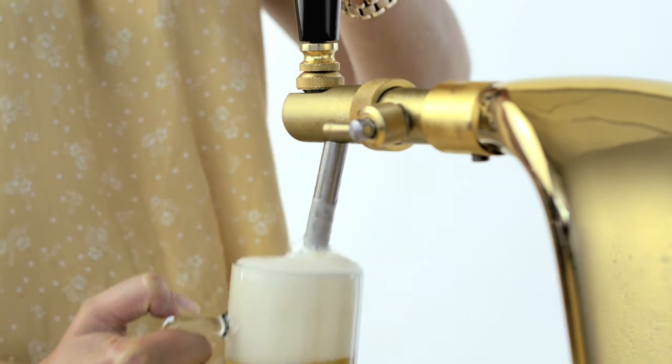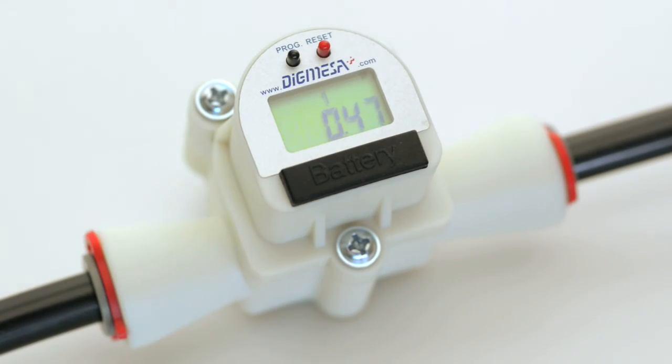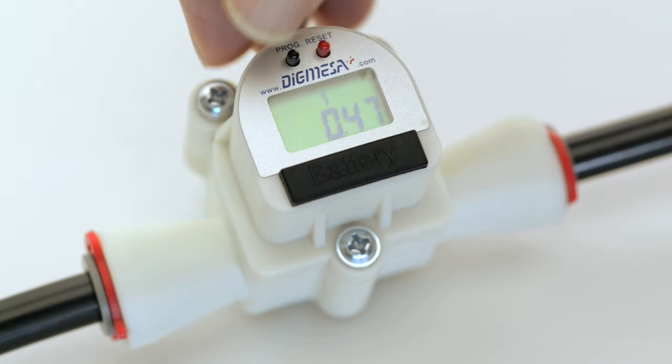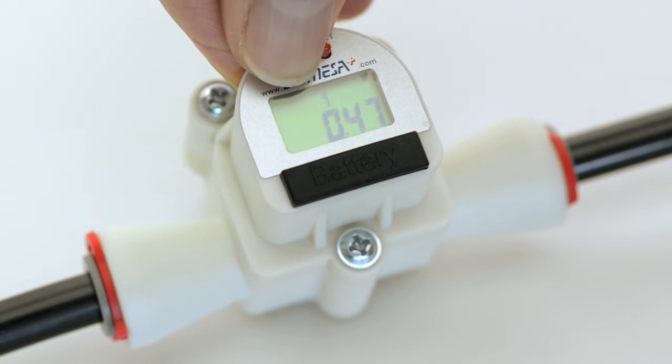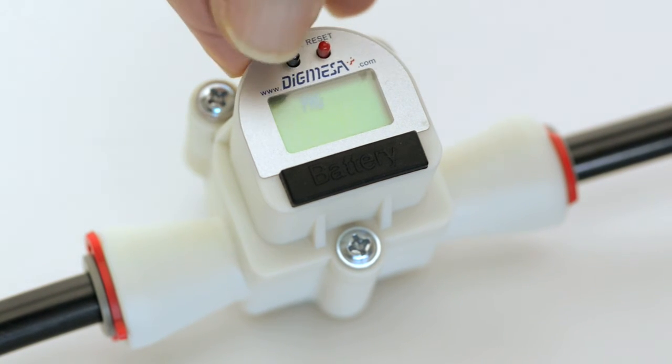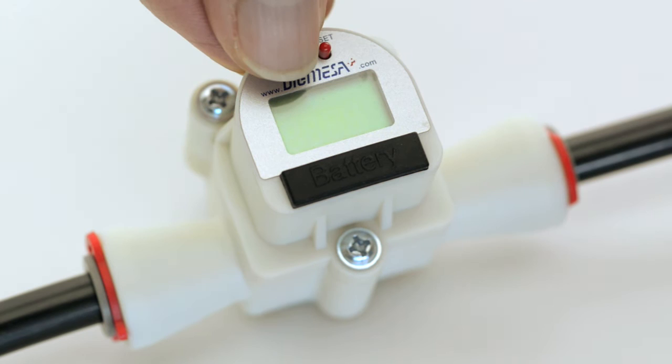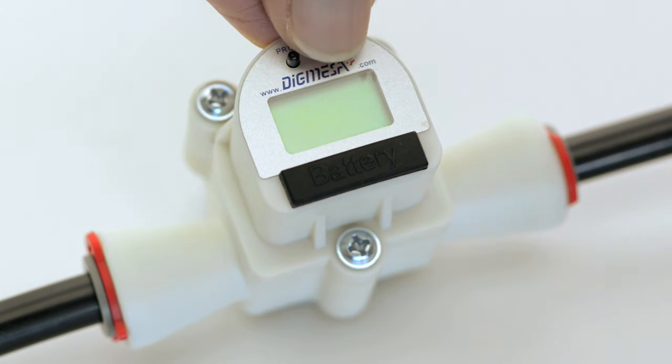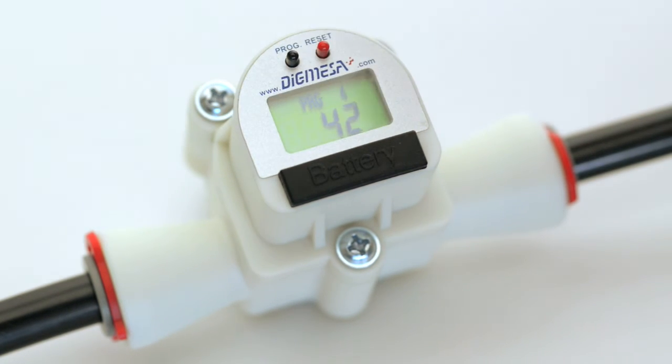To view or change the number of pulses per liter, proceed as follows. Hold the black program pin down until the message PRG flashes on the display, then release it. Now press the black program pin four times until the message PRG4 flashes. Then press the red reset pin once. PRG4 ceases to flash and the number of pulses per liter is displayed.